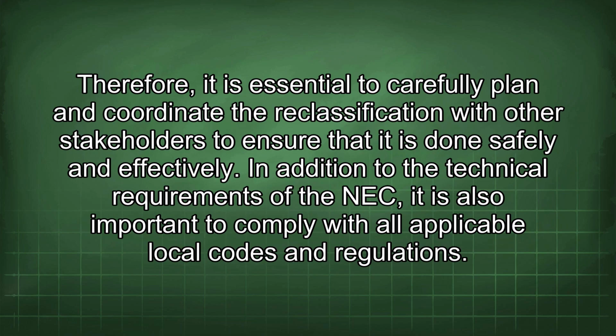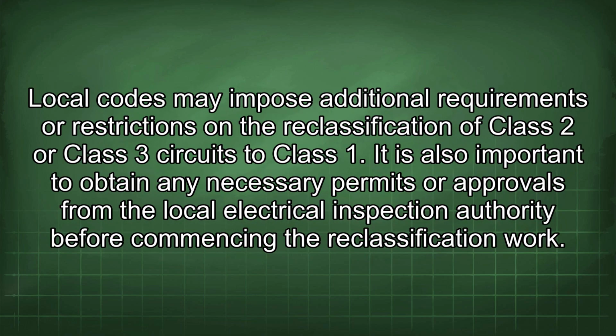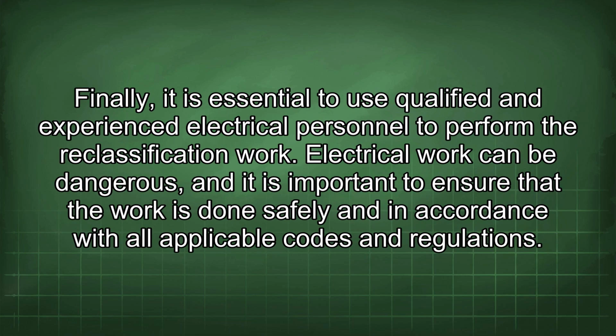Therefore, it is essential to carefully plan and coordinate the reclassification with other stakeholders to ensure that it is done safely and effectively. In addition to the technical requirements of the NEC, it is also important to comply with all applicable local codes and regulations. Local codes may impose additional requirements or restrictions on the reclassification of Class 2 or Class 3 circuits to Class 1. It is also important to obtain any necessary permits or approvals from the local electrical inspection authority before commencing the reclassification work. Finally, it is essential to use qualified and experienced electrical personnel to perform the reclassification work.